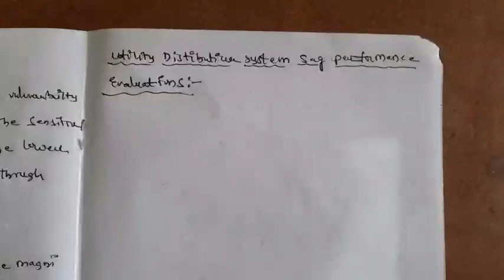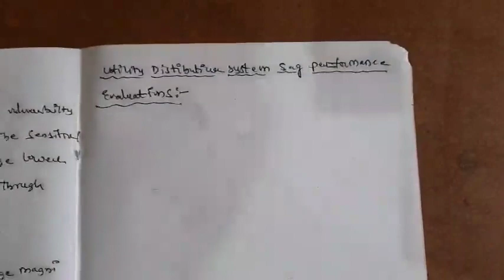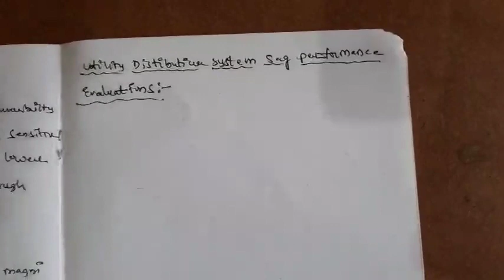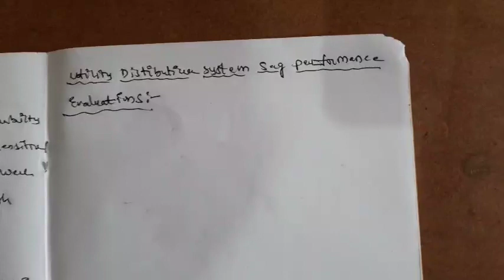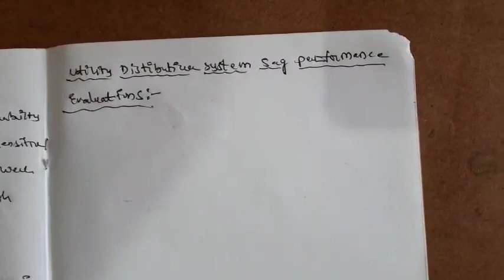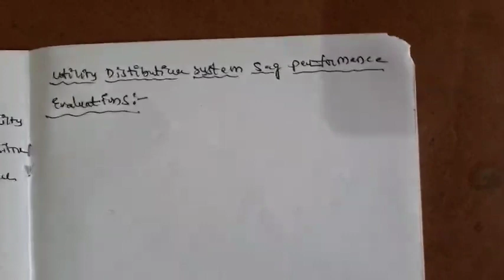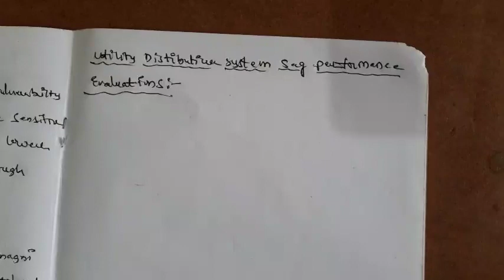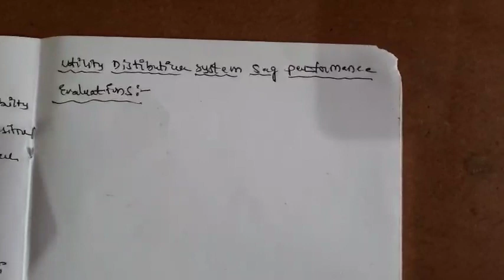During this class we discuss what the sources of sag are. For that we can consider one distribution system. The sources are faults on the same feeder, faults on the parallel feeder, and faults on the transmission system. Faults on the same feeder can cause voltage interruption. Faults on the parallel feeder cause voltage sag. Faults on the transmission system also cause voltage sag. So during this we can evaluate the overall voltage sag performance at the end user facility, which is a combination of both.